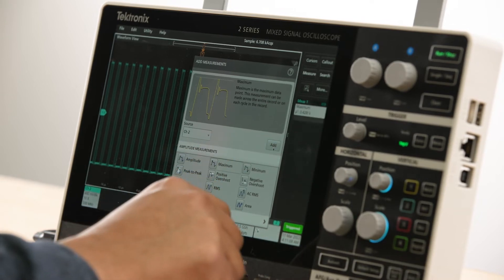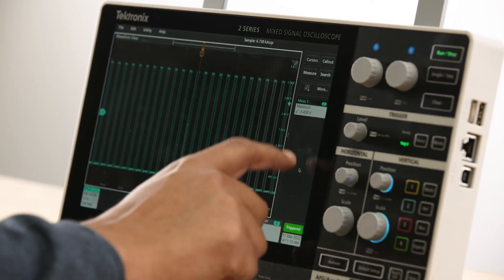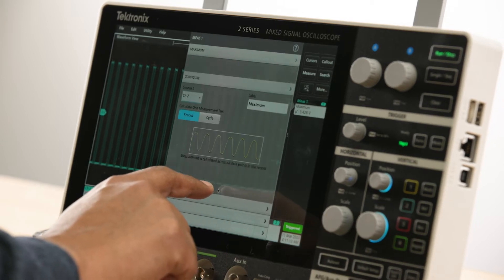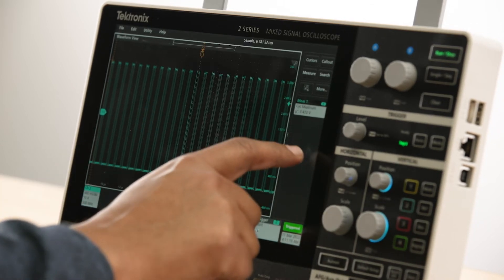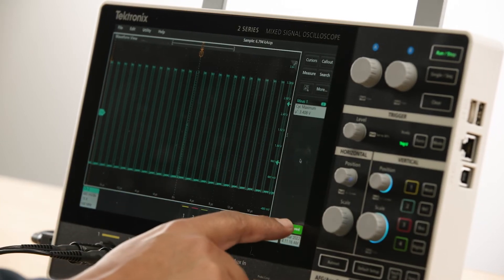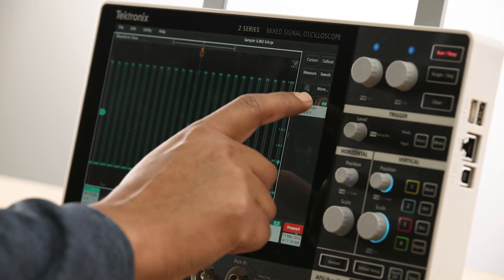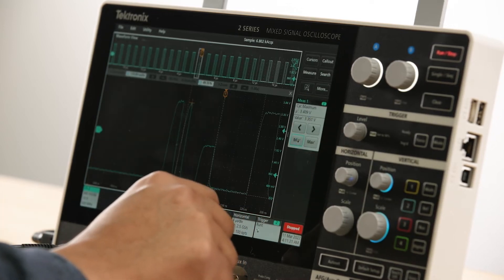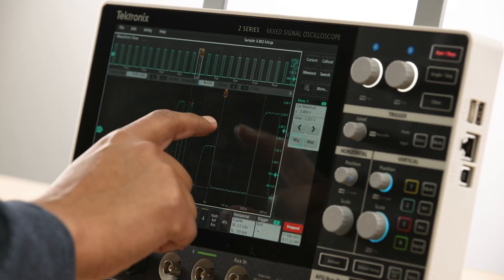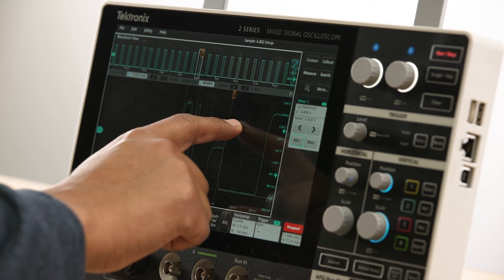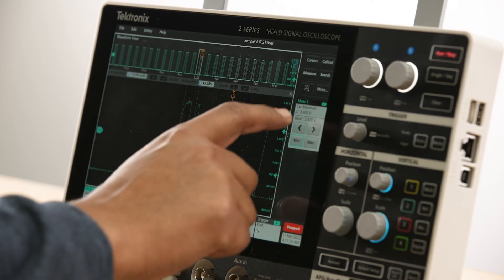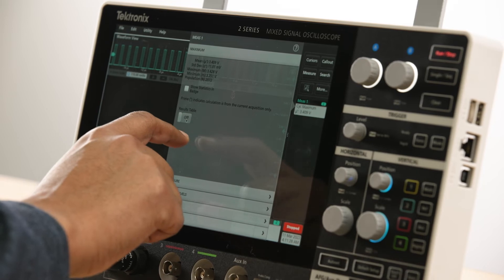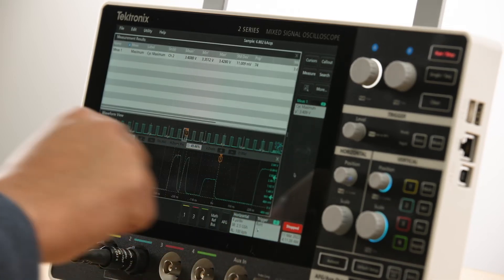Unlike other scopes in the market, measurements on the 2 Series MSO are performed on the entire record, resulting in additional statistics that can give you more insights and help you quickly navigate to any measurement location. You can view the results on the badges or in a tabular format by turning on the results table.